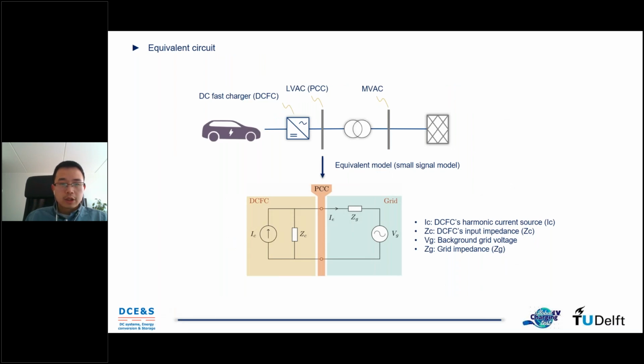In order to study the power quality issues, the system can be equivalent to such a circuit. To be more specific, the charger side, meaning the front-end rectifier of the charger, can be equivalent to a current source in parallel with the input impedance of the charger. While the grid side can be equivalent to a voltage source in series with the grid impedance. So as you can see, power quality issues at PCC can be affected by all these four elements.